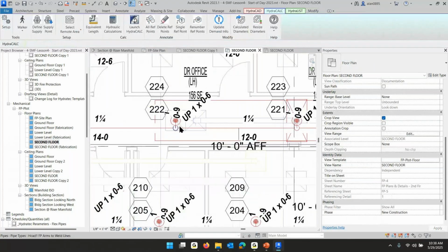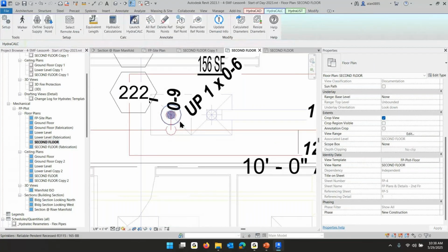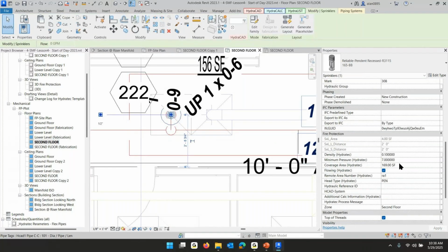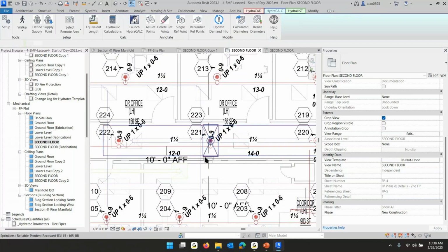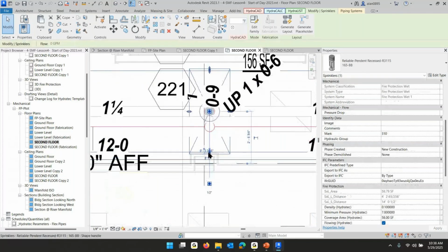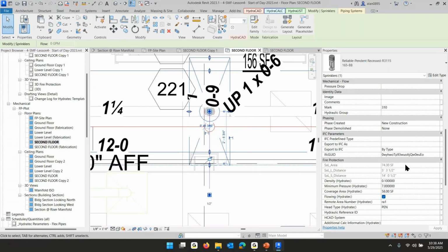And this one would be 58 also. I'm not sure you got that last head all the way to the wall. Okay, let me check. Not that it really matters. I don't think you're going to fail your inspection. You're right. I got it to this. No, I didn't get it to either wall. So 58 is a cheat. It should be 74.